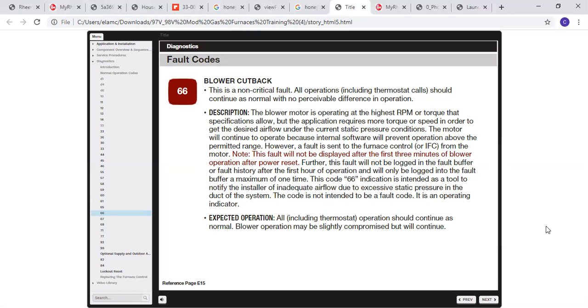If you're using an EcoNet thermostat, it will also kick back on your EcoNet as a 66 blower cutback fault. So once you get the 66, for the first 3 minutes it will show the 66, then it will disappear. Over time, if you get the 66, what you're going to notice automatically is sound. It's going to be loud. It's going to be obtrusive. That's obvious, generally speaking. Blower operation will continue. Over time, it will be compromised, but it will continue to run.